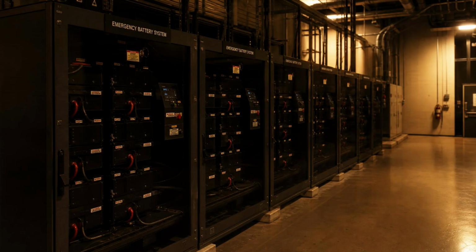Every other major component in the system involves active machinery. Generators have engines and alternators. Transfer switches have moving contacts. UPS systems have rectifiers and inverters and control electronics. Even the monitoring equipment has circuits that are continuously processing and comparing and deciding, but the battery just holds. It does not move, it does not process, it does not decide. It is a vessel of stored potential, energy that was placed inside it during the charging process, and that sits there, available, patient, present, waiting for the moment it is called upon to give itself back.